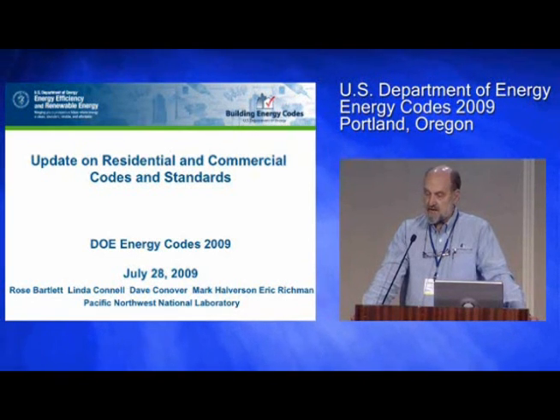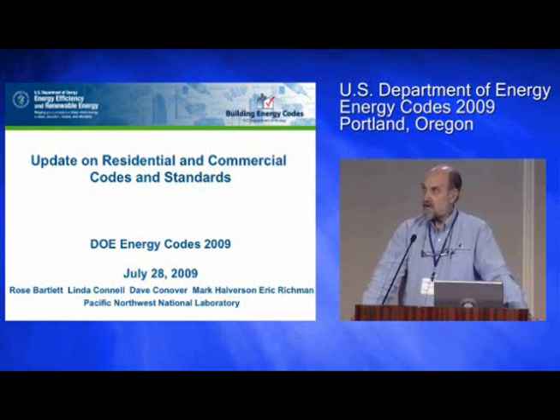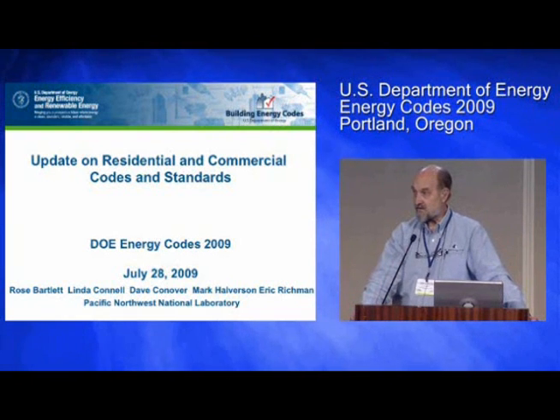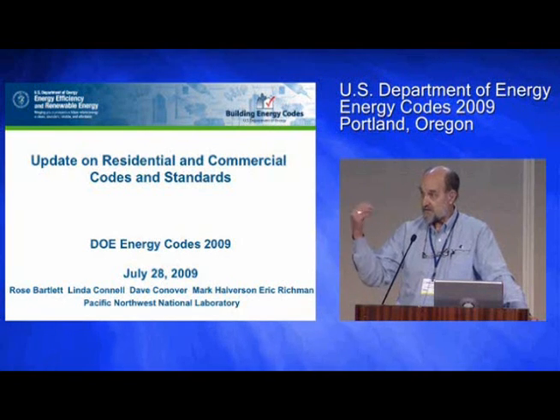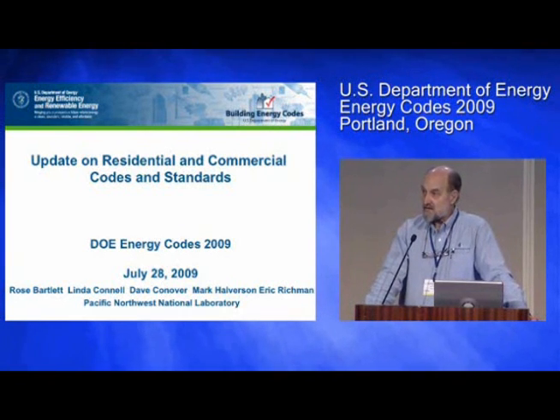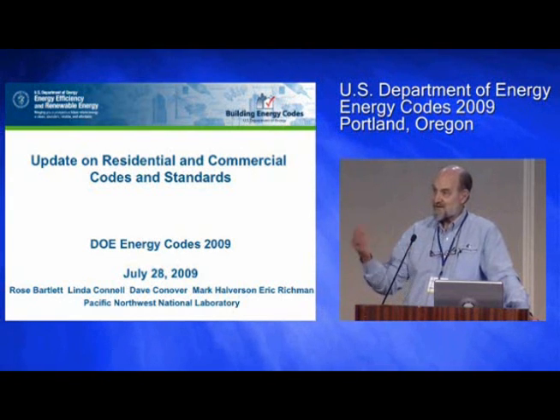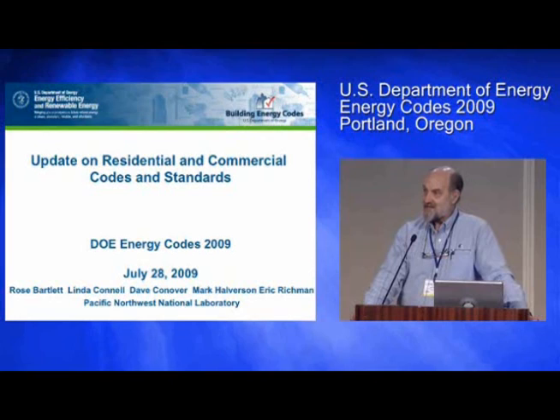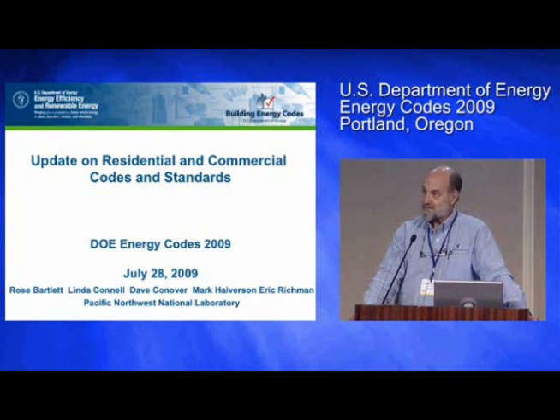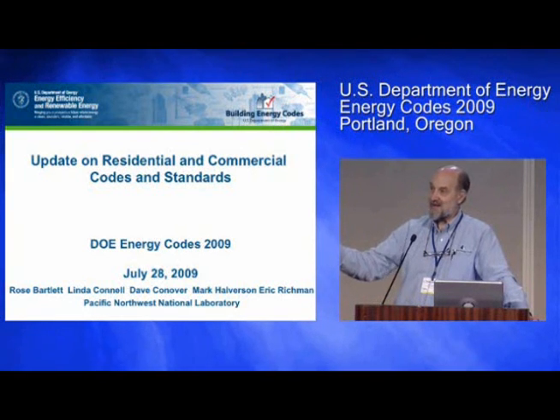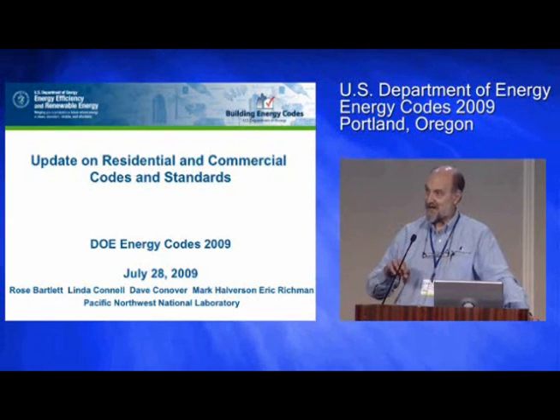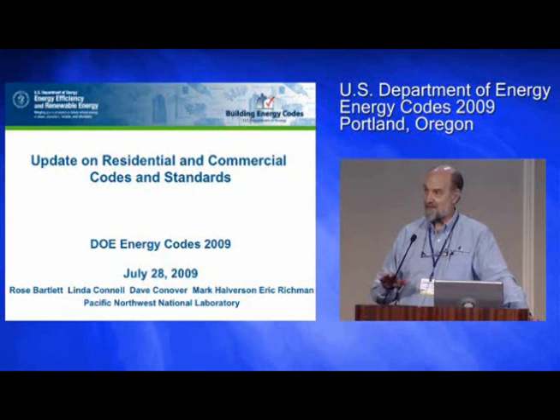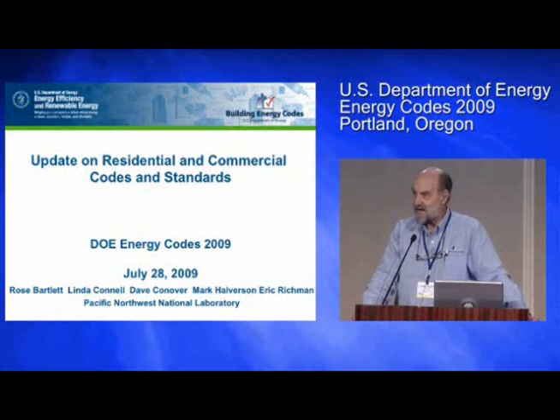Let me give you an example on that. If I can comply with the lighting requirements for this room under the ASHRAE standard, which would be by reference, I might be able to not comply with the lighting standard if I use the IECC for a particular building or a particular space. Our judgment on whether those are equivalent would be based upon the least stringent of those requirements. So just because the standard may reference either this track, ASHRAE standard 90.1, or the international track, the IECC, doesn't make them equivalent. I might be able to go one way and it may be more stringent, or it may be less stringent, and that would be the governing factor. Thank you very much.